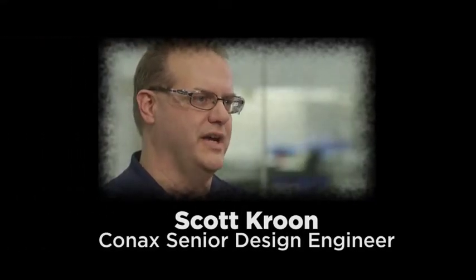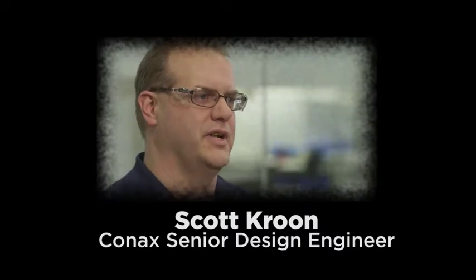Conax Senior Design Engineer Scott Kroon was responsible for coordinating the field testing of coated thermocouples at a major fab. EtchDefender was tested at a world-leading operator of epitaxial reactors. They closely monitored their product and their process for any sort of contamination, and none was found. No changes to the reactor settings are required.